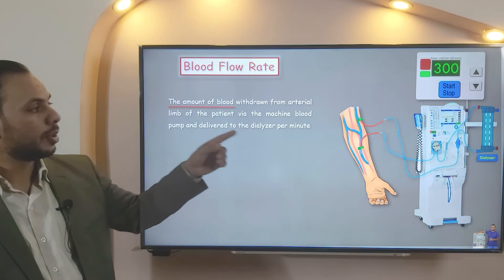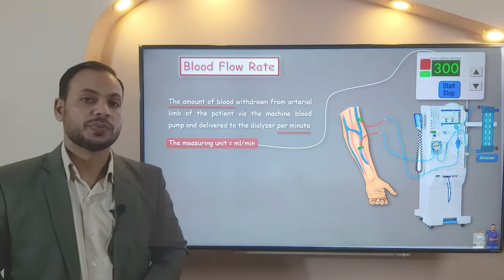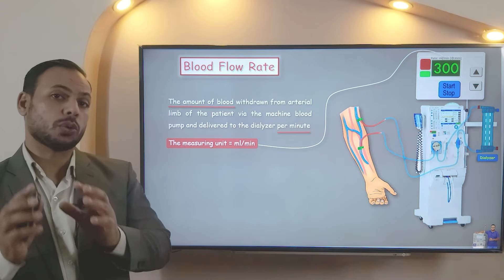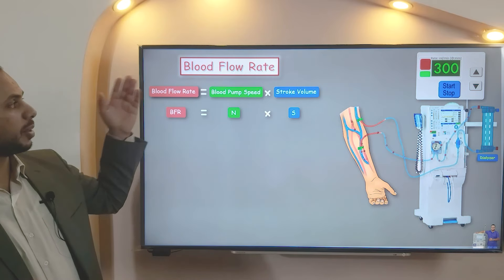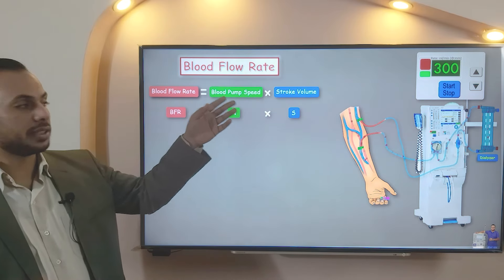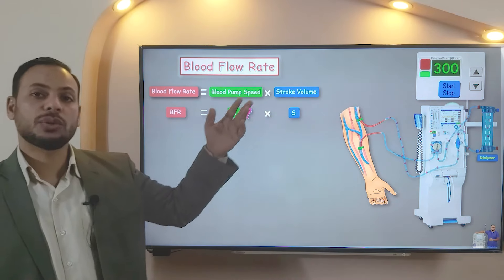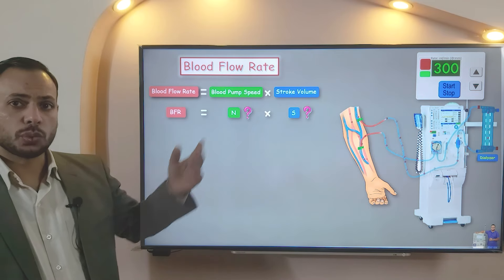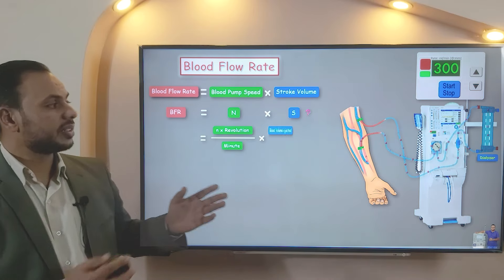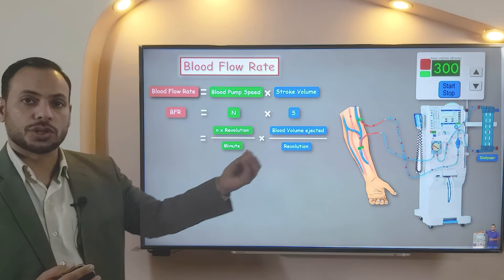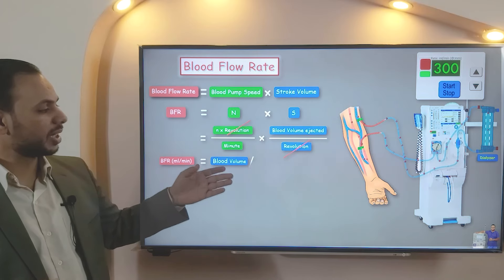Amount of blood per minute — it makes sense for the measuring unit to be milliliters per minute. Now, let's formulate an easy and simple equation. The blood flow rate equals the blood pump speed multiplied by the stroke volume. Let's symbolize the blood flow rate as BFR, blood pump speed as N, and stroke volume as S. N, the pump speed, will be the number of revolutions per minute. S, the stroke volume, is simply the volume of blood ejected with each revolution. Canceling 'revolution,' the blood flow rate equals blood volume per minute — makes sense.